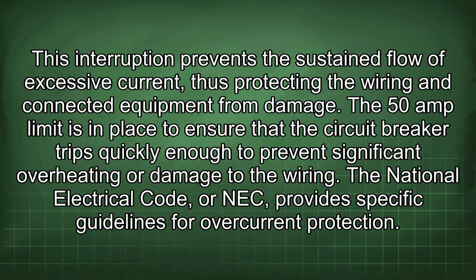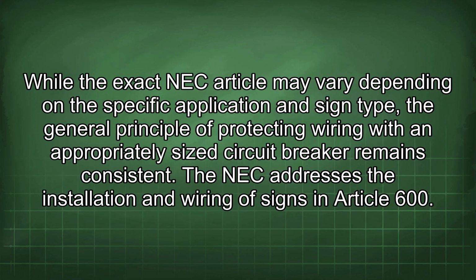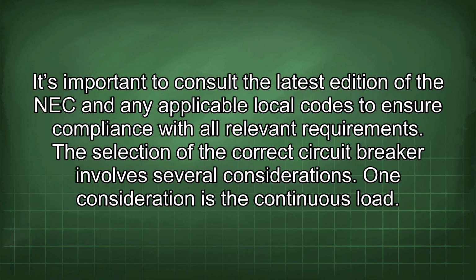The National Electrical Code, or NEC, provides specific guidelines for overcurrent protection. While the exact NEC article may vary depending on the specific application and sign type, the general principle of protecting wiring with an appropriately sized circuit breaker remains consistent. The NEC addresses the installation and wiring of signs in Article 600. It's important to consult the latest edition of the NEC and any applicable local codes to ensure compliance with all relevant requirements. The selection of the correct circuit breaker involves several considerations.